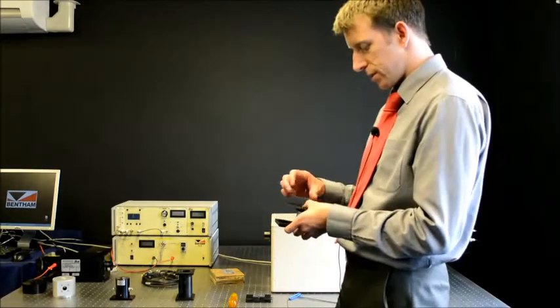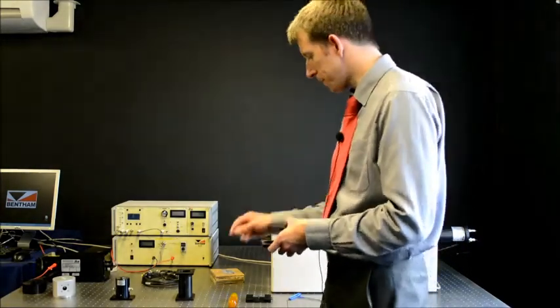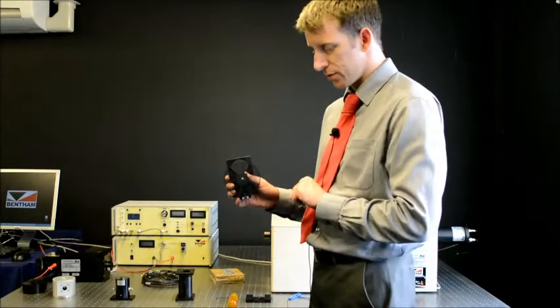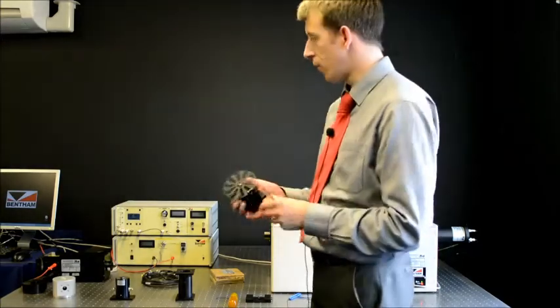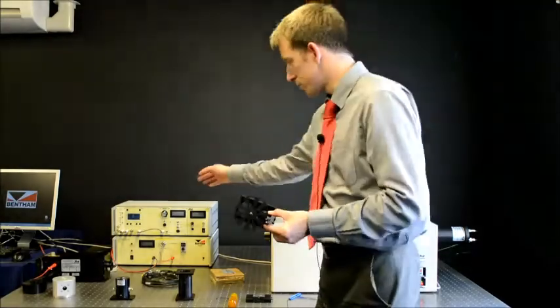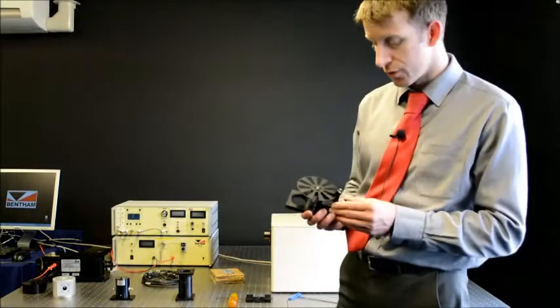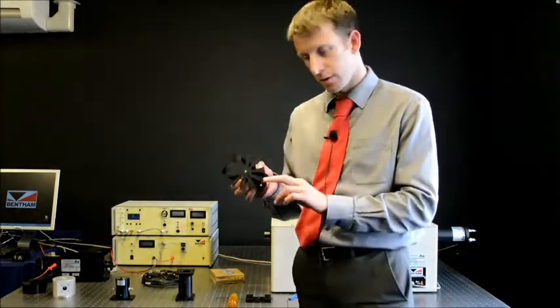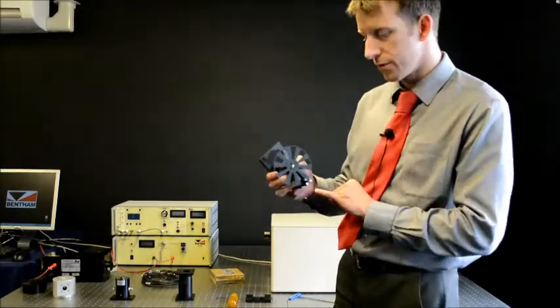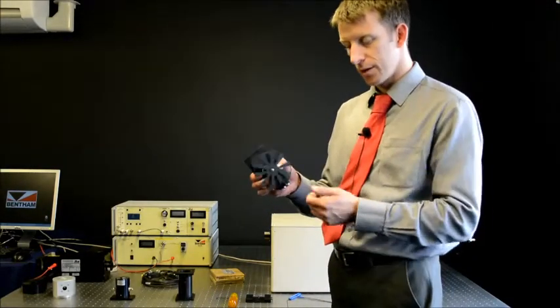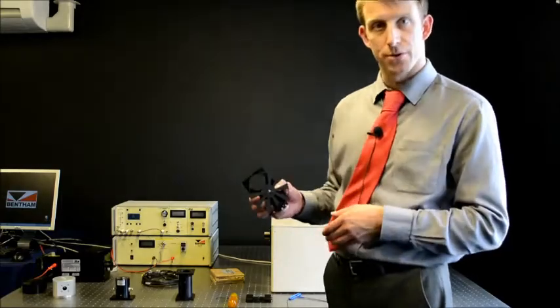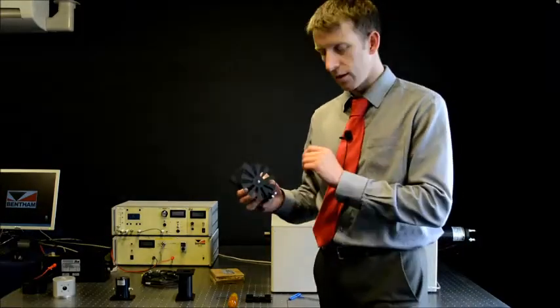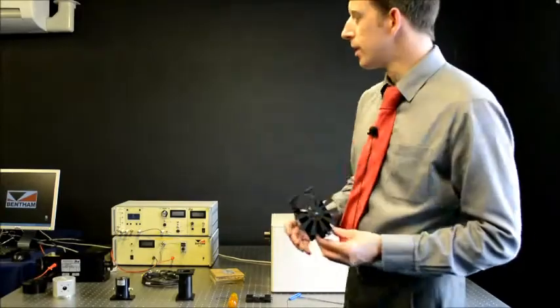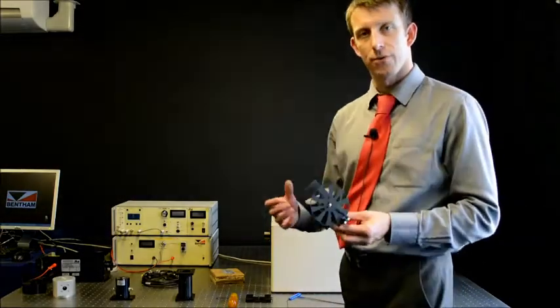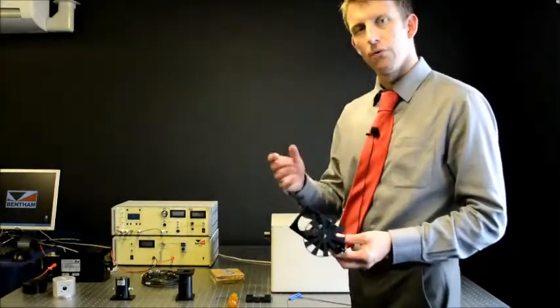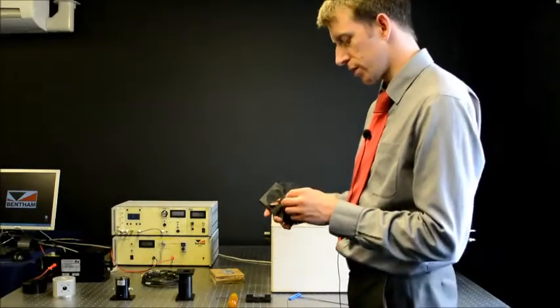So we've fitted the blade, and the optical chopper is driven by a DC motor with power provided from the 218 module, the optical chopper controller. To the base of the optical chopper is an IR emitter receiver, so that as the blade turns, the IR emitter receiver output varies accordingly, and that is returned to the detection electronics as a reference. So that is the known frequency of chopping the source under test.